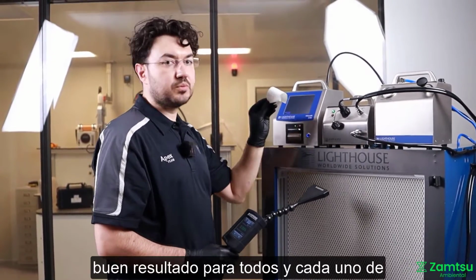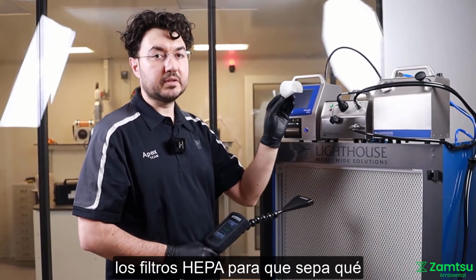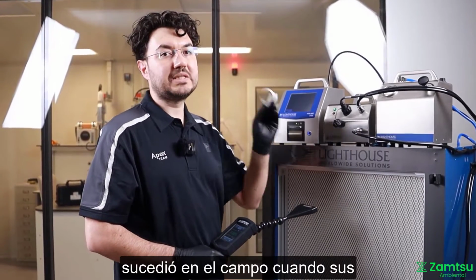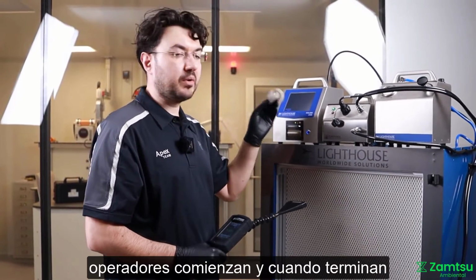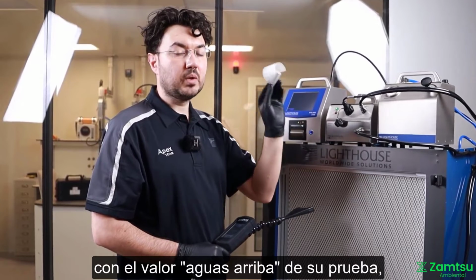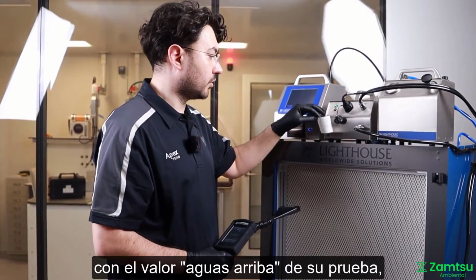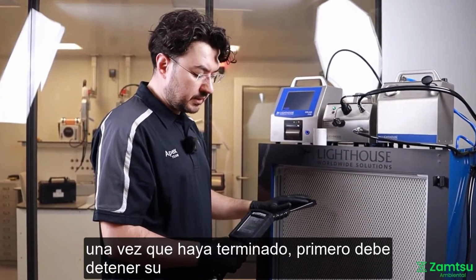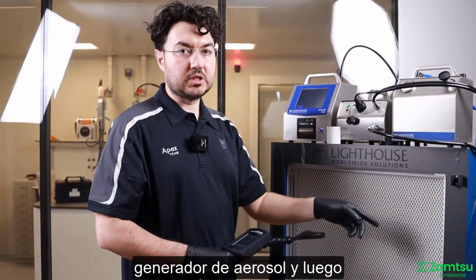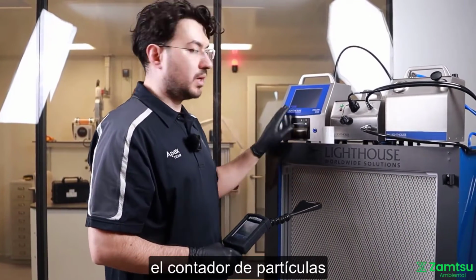This is a nice output for each and every HEPA filter, so that you will know what happened in the field, when your operators started and when they finished, with the upstream value of your testing. Once you're done, you have to stop your aerosol generator first, then the particle counter.